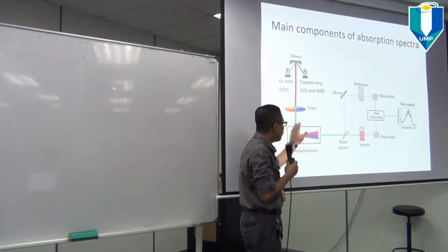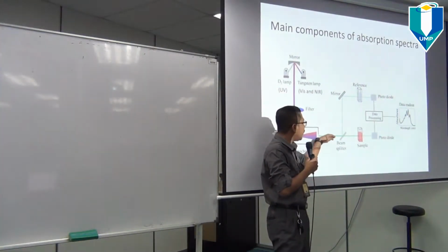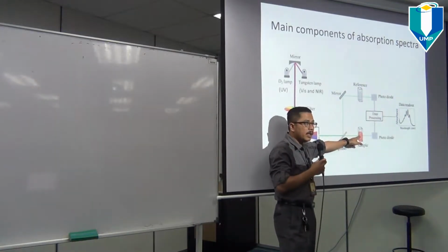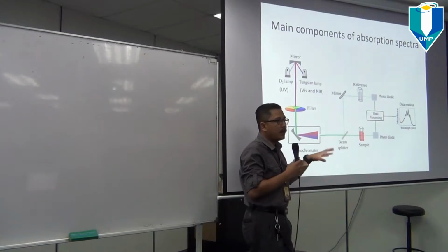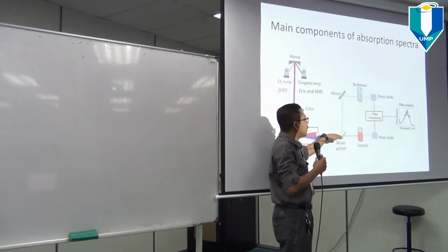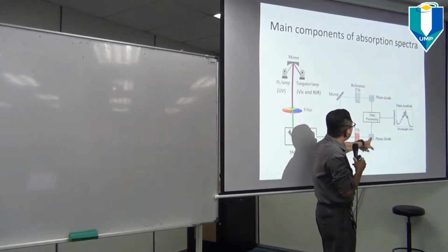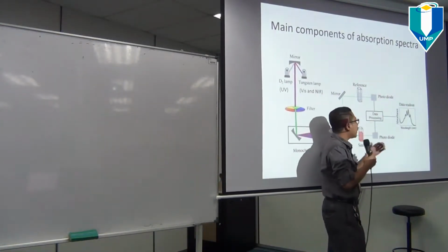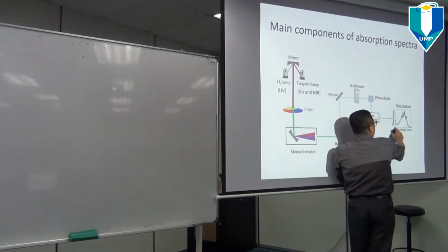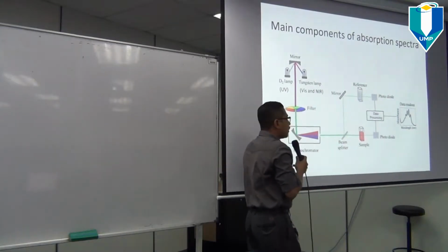So the function of the monochromator is to filter out which light should pass through the monochromator and beam splitter to the sample. If we want to plot a graph which corresponds to x equals 200 nanometer, we should pass the 200 nanometer light and it goes to the sample and goes to the photoarray, which is the sensor, and produces the graph. One plot for 200 nanometer, we should get one point over here. Then it goes to the second round.